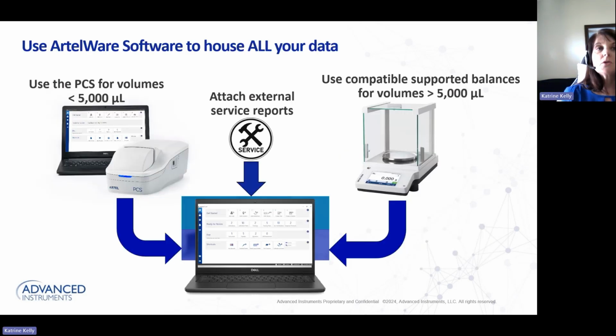So with the PCS, your results are traceable from 0.1 microliter up to 5,000 microliters. If you ever send your pipettes out for repair and maintenance, you can upload a PDF copy of your external reports and results to the software. And most recently, the software can integrate with balances to read volumes greater than 5 ml.